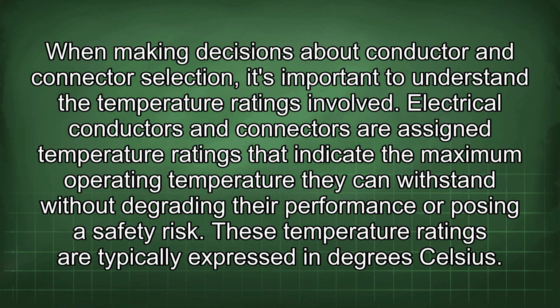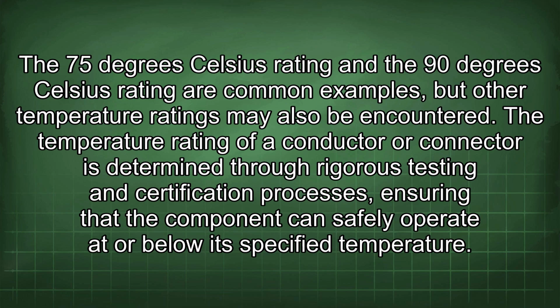When making decisions about conductor and connector selection, it's important to understand the temperature ratings involved. Electrical conductors and connectors are assigned temperature ratings that indicate the maximum operating temperature they can withstand without degrading their performance or posing a safety risk. These temperature ratings are typically expressed in degrees Celsius. The 75 degrees Celsius rating and the 90 degrees Celsius rating are common examples, but other temperature ratings may also be encountered. The temperature rating of a conductor or connector is determined through rigorous testing and certification processes, ensuring that the component can safely operate at or below its specified temperature.